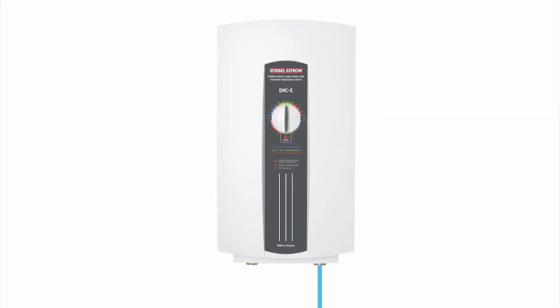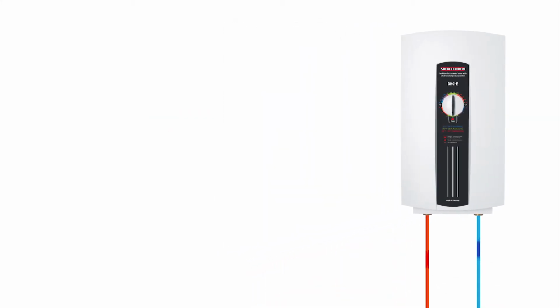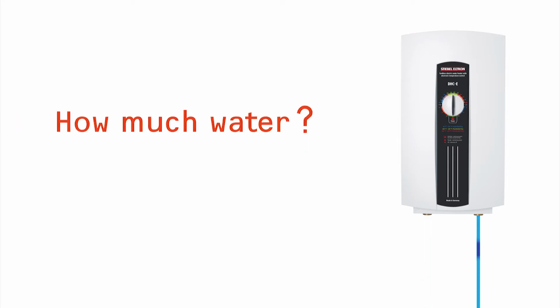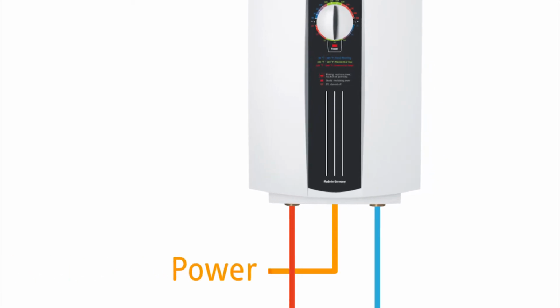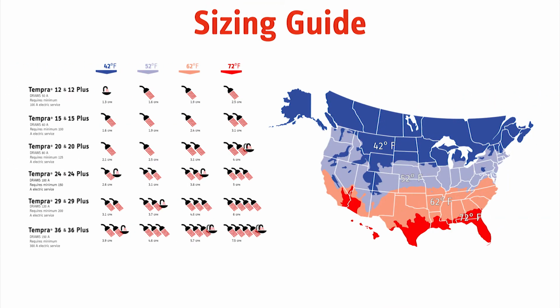We know that a tankless water heater can provide endless hot water. But how much water is that? What is its maximum flow rate? The answer depends on how powerful the water heater is, and what temperature rise is needed: the difference between the temperature of the incoming cold water and the temperature of the hot water needed. This sizing decision is made easy with our sizing charts.